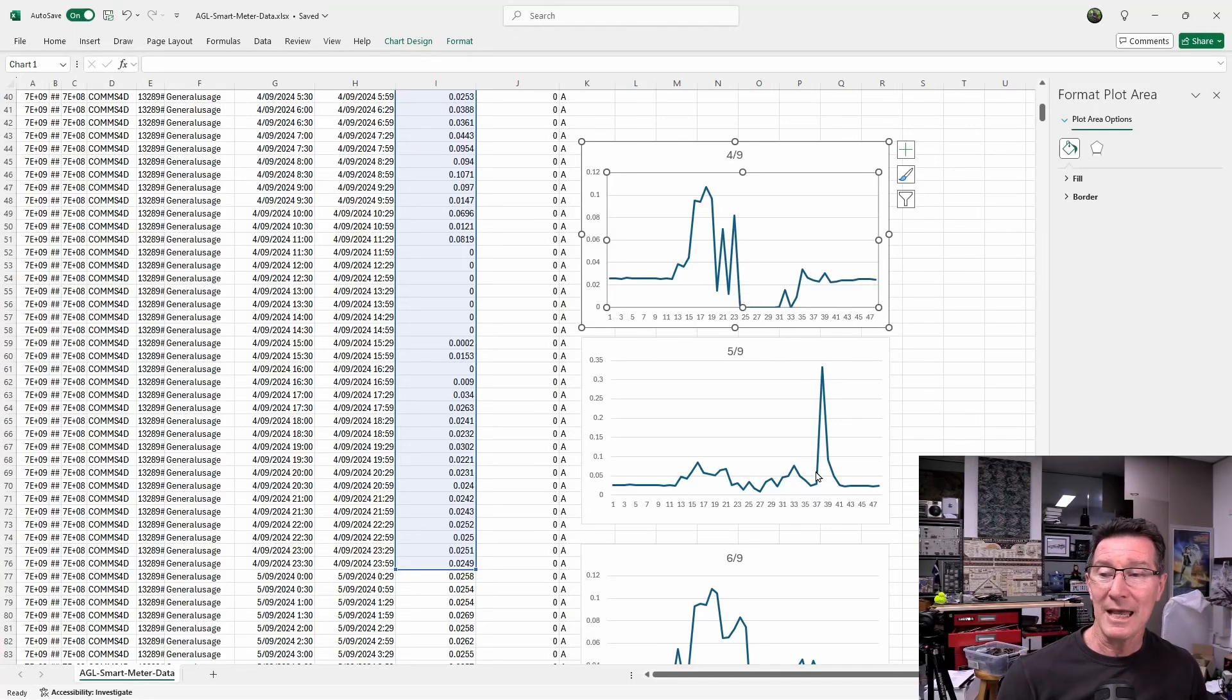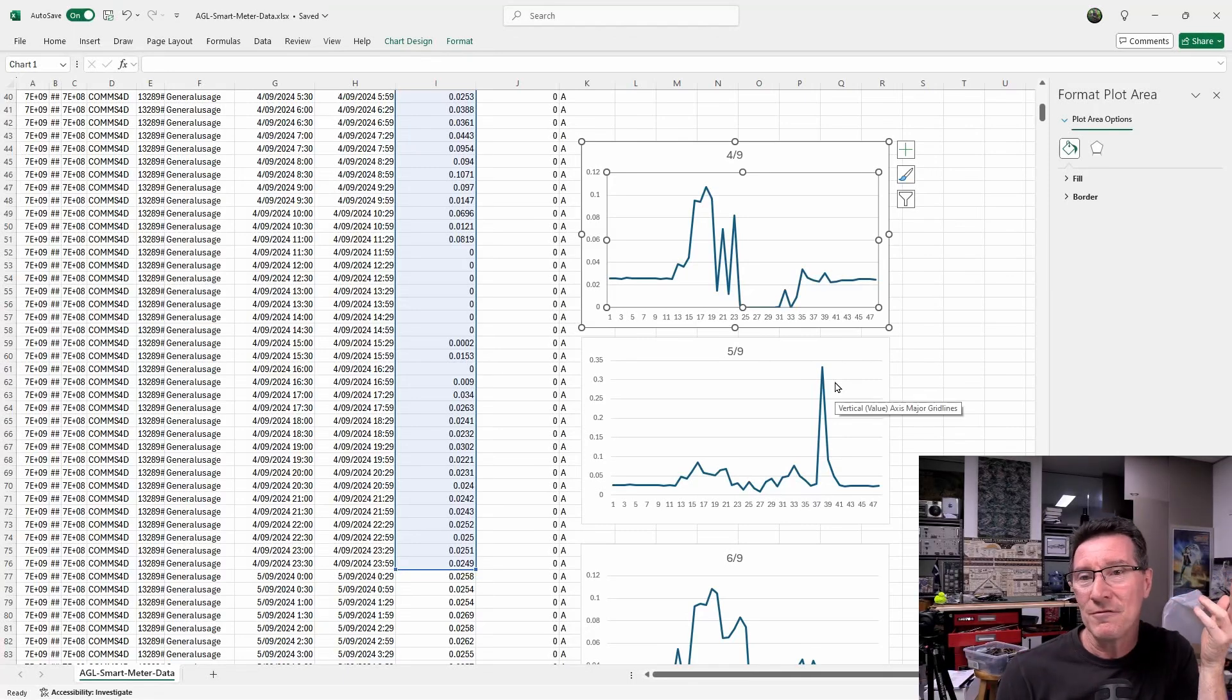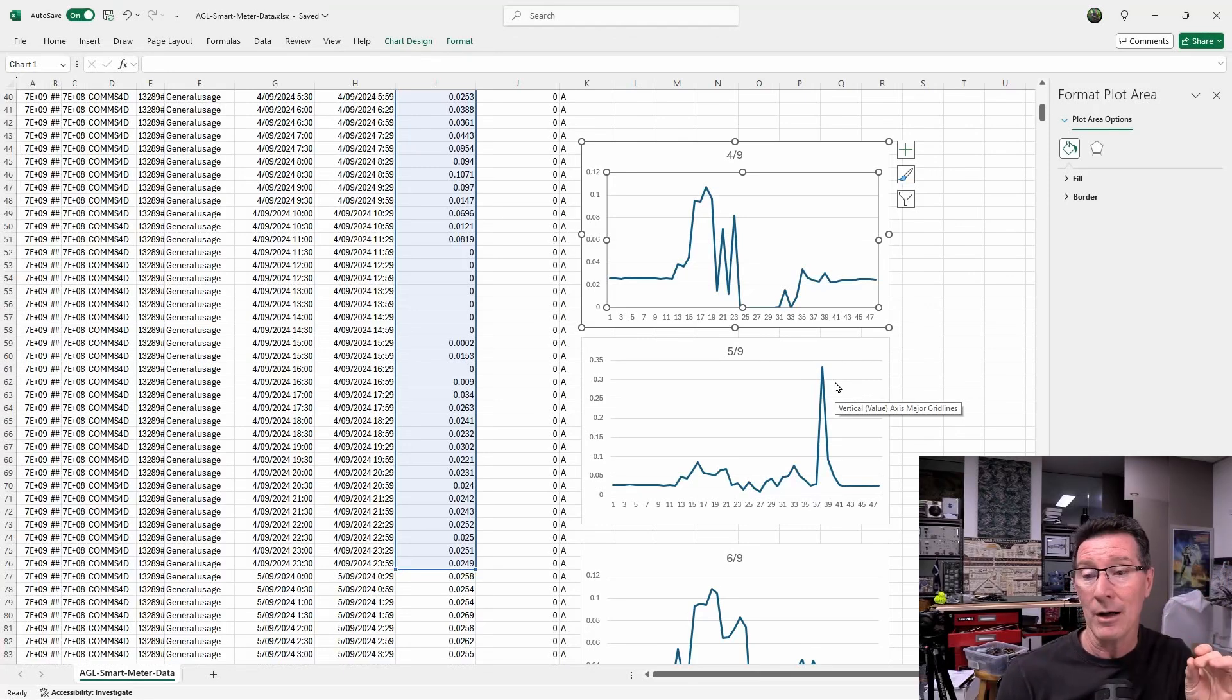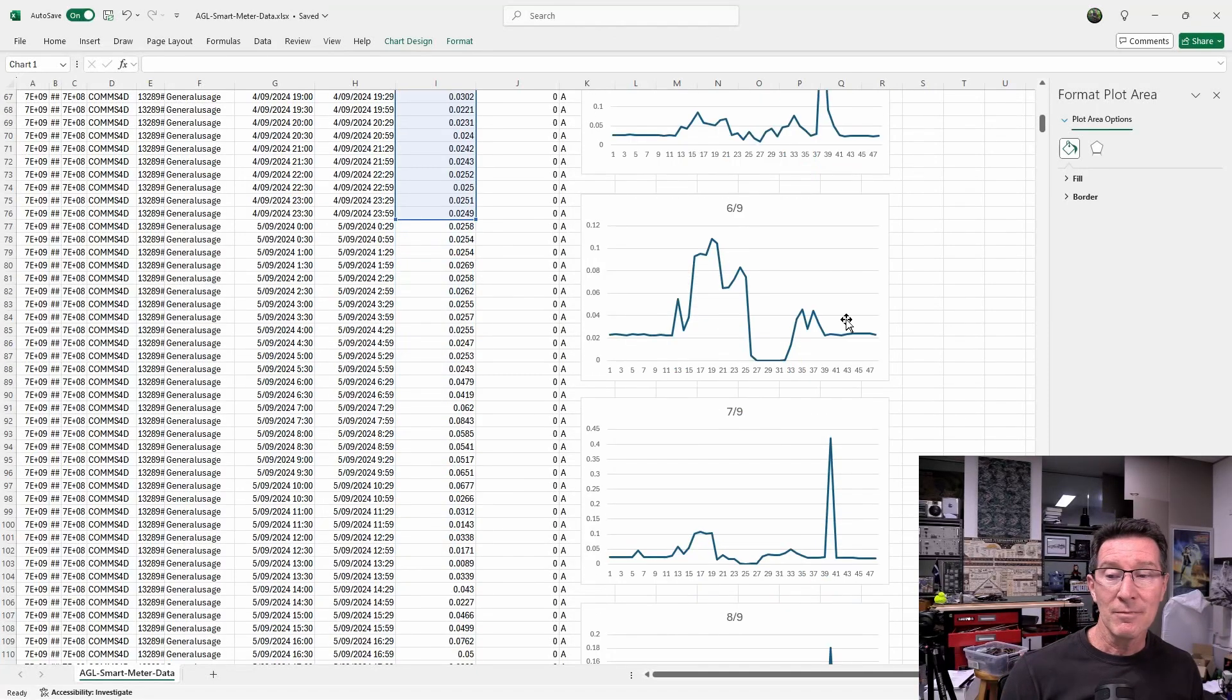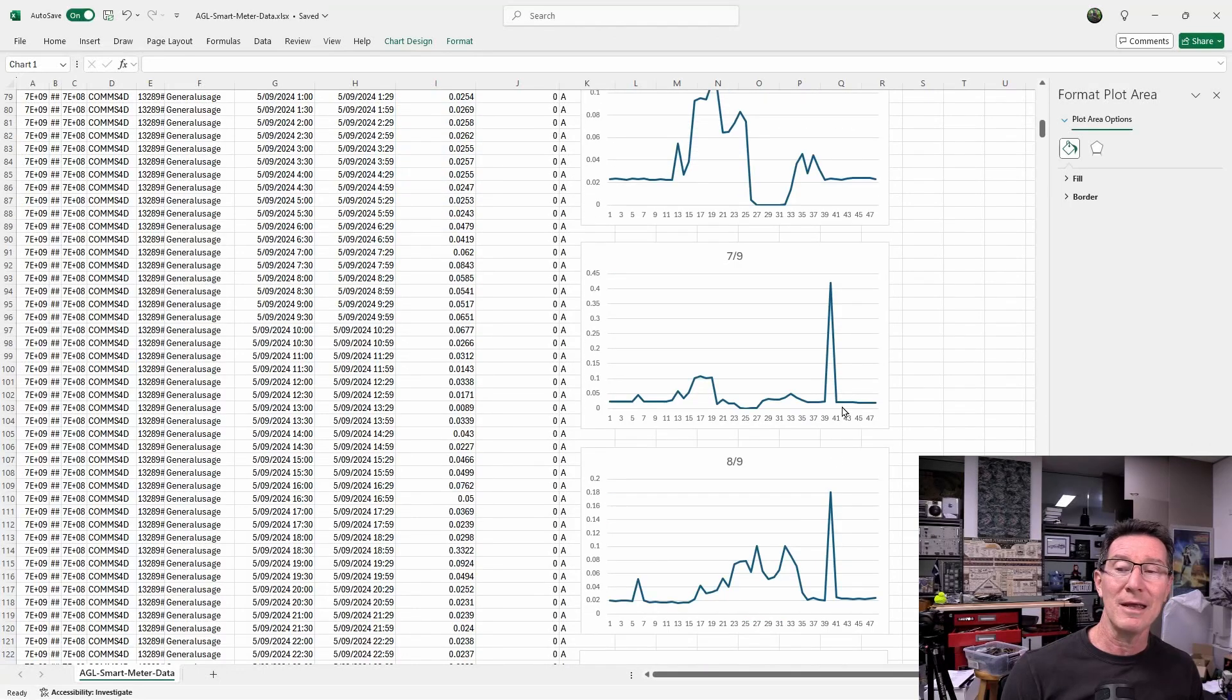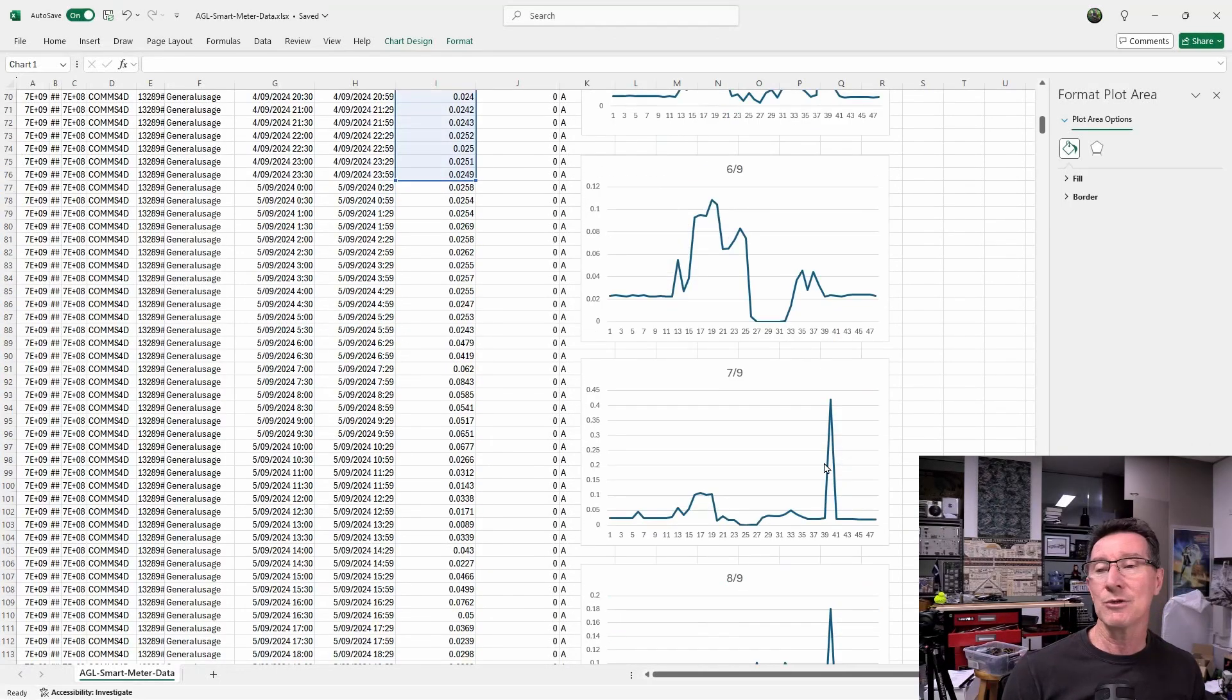Now, there's a big spike here. Presumably we switched on something, and its peak current might have been for 10 minutes above what my battery can provide, which is 5 kilowatts power max. So this is at night time, and curiously, there's several spikes at a similar time here.